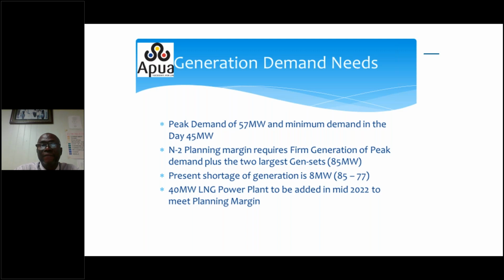We have 77 megawatt of firm capacity, so we're presently short of 8 megawatt, and that is really to take care of the reserve capacity. Now, the government has a very aggressive housing program, which means that the load is going to be increasing at a very rapid rate. There are also some improvements that are going to be taking place in the hotel industry. Some of the hotels are having expansion, and the island's port is doing a major expansion. So we see the need for additional generation immediately.